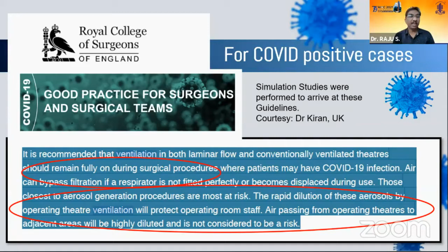However, if at all we want to add a negative pressure, we can do it without modifying the existing OT by adding what is called an airlock. So if you have a room adjacent to the OT, a negative pressure sink can be created to prevent the spread of infection. In the room adjacent, a powerful exhaust with the HEPA is added. This will suck the air out of that room. The OT will continue to be at positive pressure, and the adjacent area will also remain the same. And this negative pressure sink will prevent the infective air from the OT getting onto the general outside area.